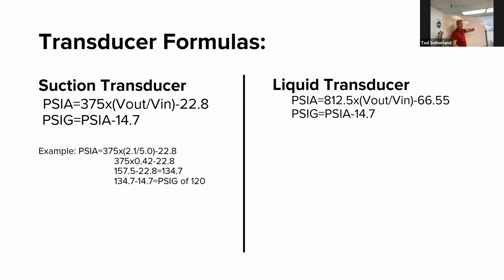Now that's PSIA. So to adjust from PSIA to PSIG, we need to subtract 14.7 PSI. So 134.7 minus the 14.7 equals 120 PSIG. And that's what you should be reading on your suction pressure gauge or real close to it, allotting for the distance of the interconnecting tubing from the indoor unit to the outdoor unit. Any questions on that formula? I know it's a lot, but again, we can send this out to you so you have that formula. Anytime you need these formulas, you can reach out to myself, you can reach out to Tim Murphy, Brad Evans. Those are our 2 tech support guys. They're very well versed in this equipment as well, but those are your formulas.